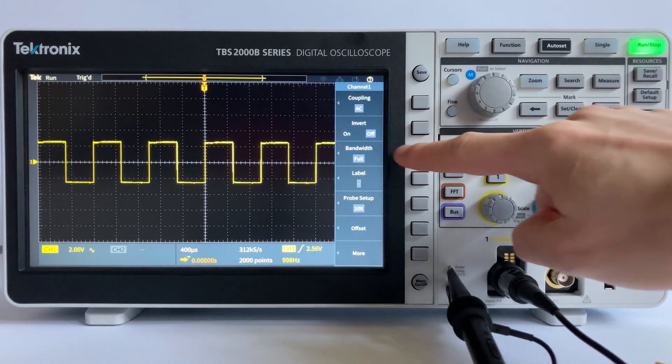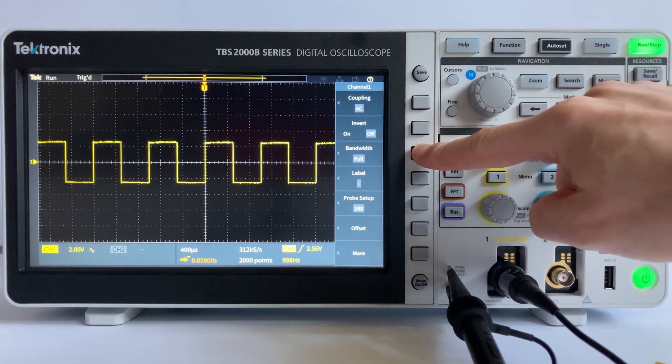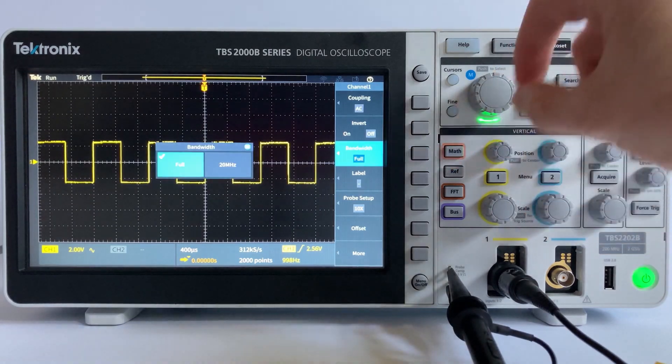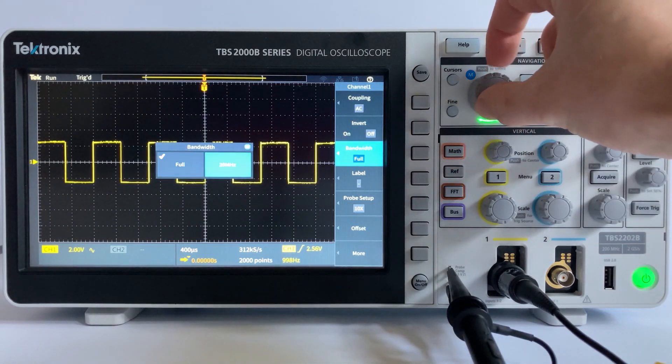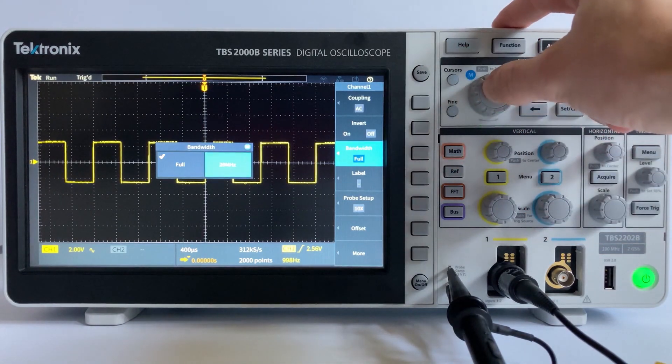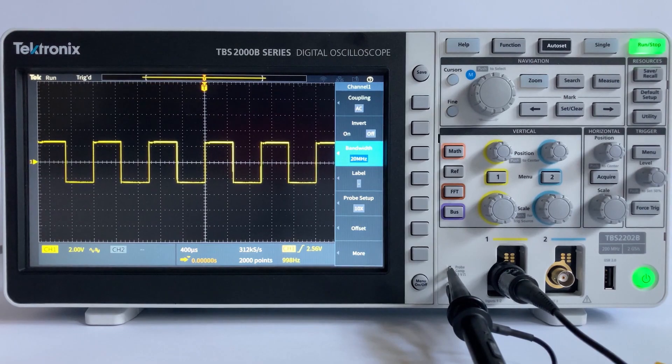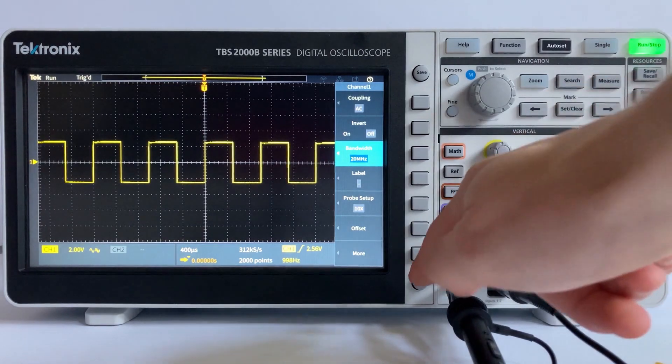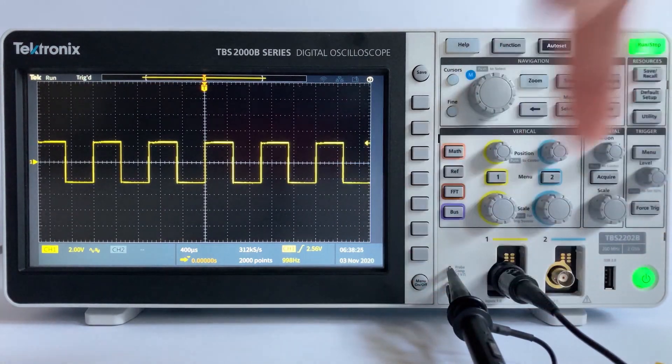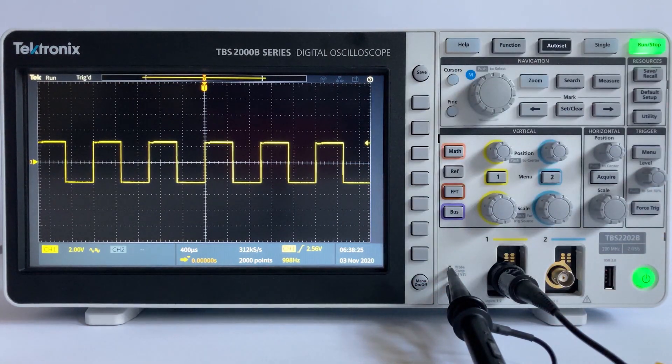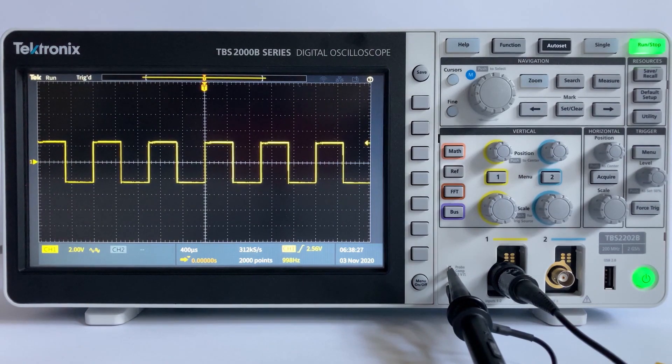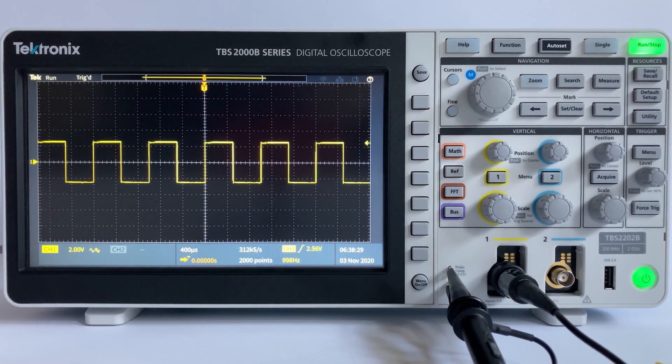Bandwidth. Most oscilloscopes have a circuit that limits the bandwidth of the oscilloscope. By limiting the bandwidth, you can reduce unwanted noise that appears on the displayed waveform, resulting in a cleaner signal display. It should be noted that while eliminating noise, the bandwidth limit can also reduce or eliminate high frequency signals and content.